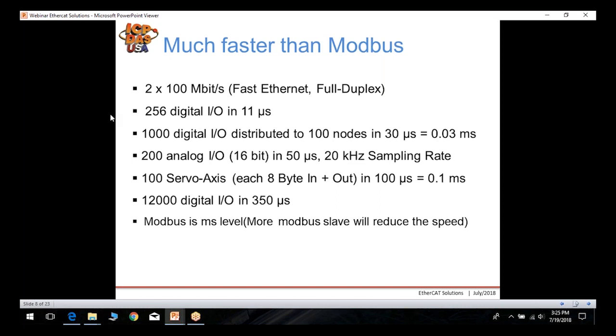Up to 200 analog I/O with 16-bit data can be transmitted to each node in 50 microseconds, or up to 100 servo devices in only 100 microseconds. Modbus operates at the millisecond level, so it is much much slower, and adding more Modbus slave devices will further reduce the speed.